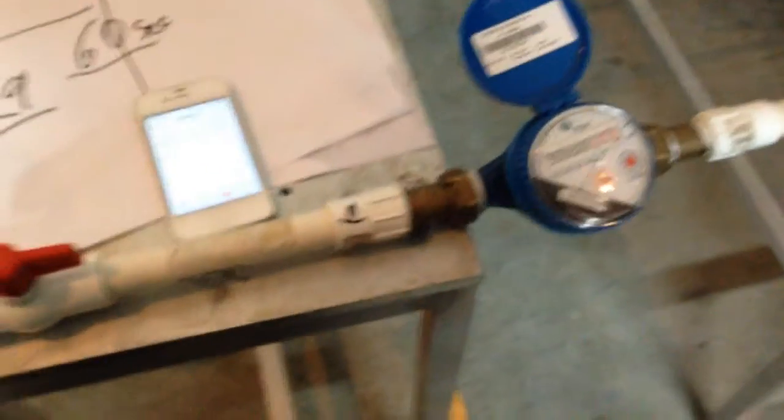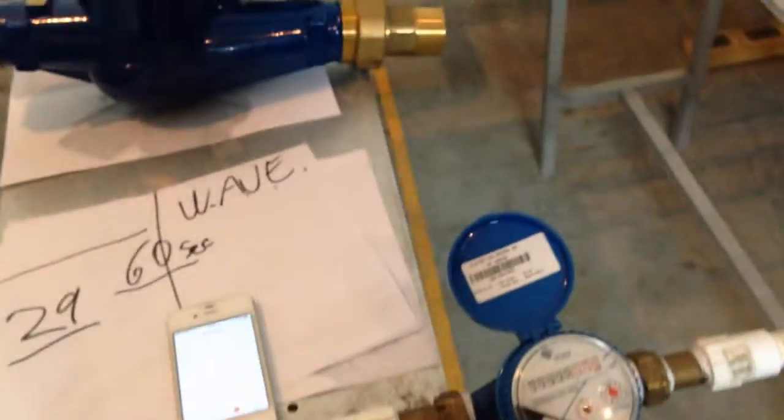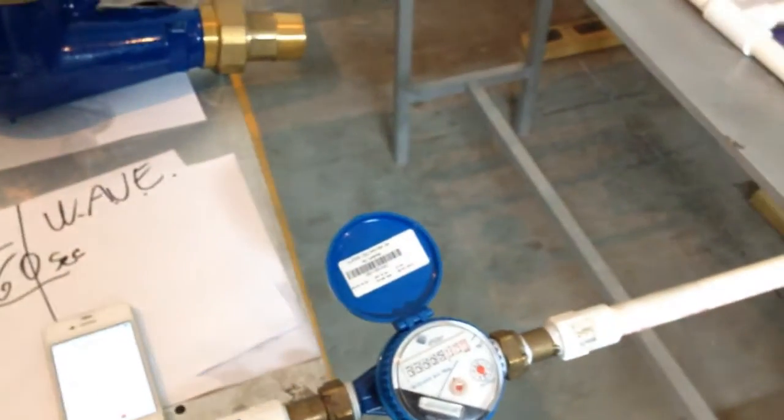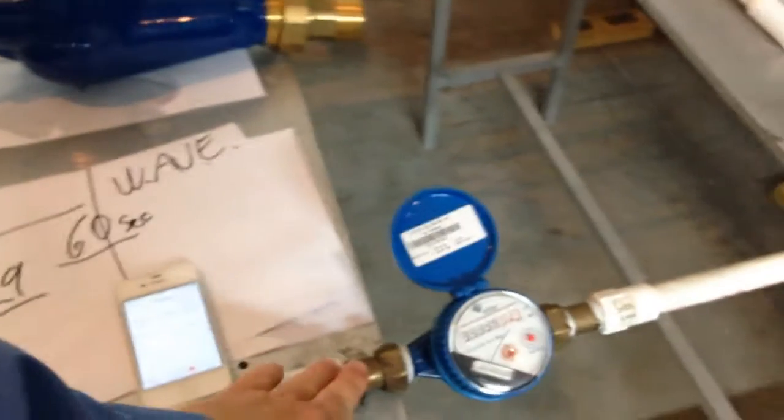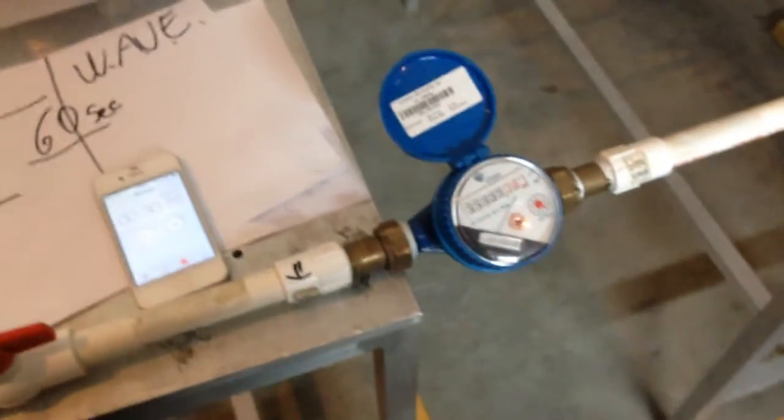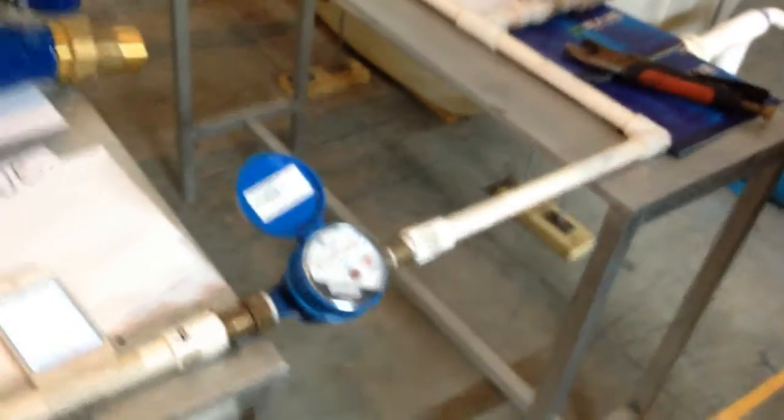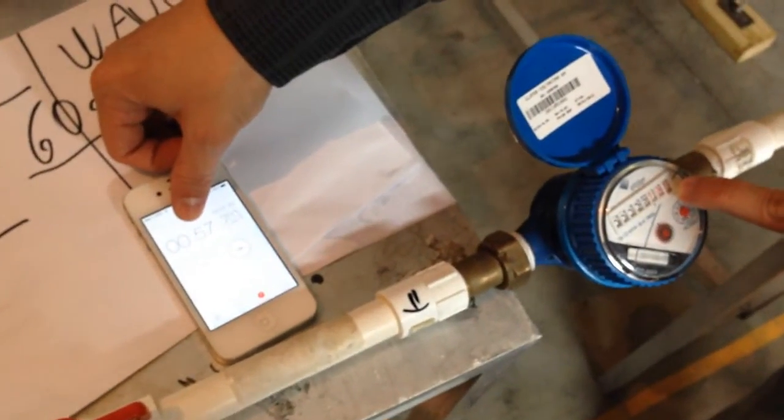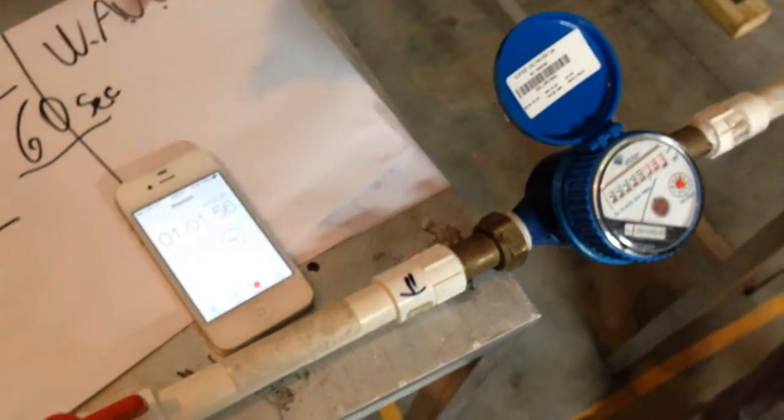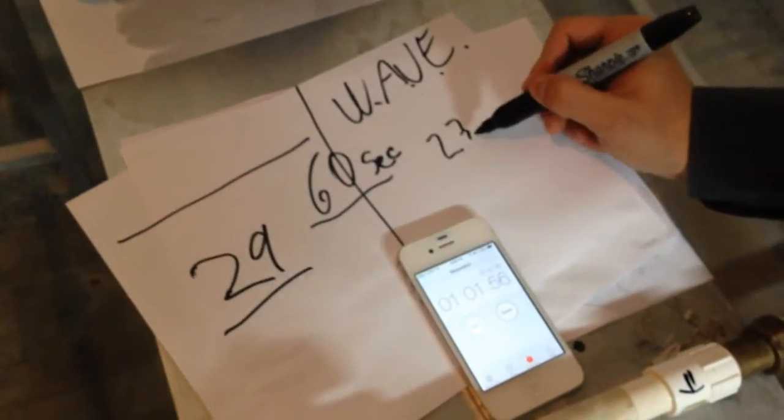So right now we can hear the sound. It's normally holding the spring. It's compressed, it's moving back, it's trying to hold the air in the line. The spring itself is also made with stainless steel? Yeah. Is it the same type of spring in each? Yes. So the only difference is the casing. It's the same material, different range, different wire, different free length. But the quality of the spring in here and the quality of the spring in the metal is the same. That's part of the precision of the production. We make sure that everything is made in the USA, we make sure the power and the quality of the material is the best one. Then you can see right here, we started at 70. So right now it's 23. So it was 23 with the valve and 29 without the valve. So 26% savings, 20.68% savings.